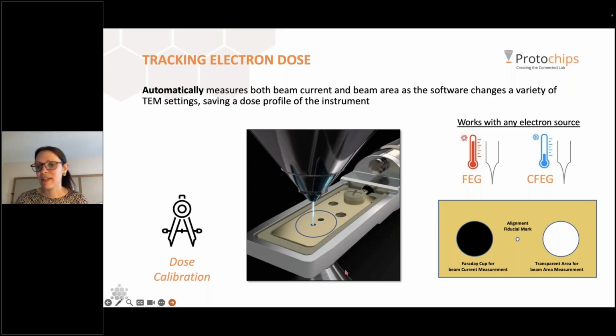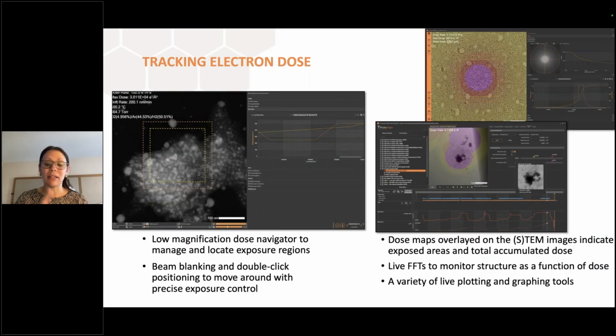Then you would remove this Faraday cup holder from the microscope and put the Triton holder in, or you could put one of your standard holders in, and you would have automated dose calculations and automated dose alignment with all of your images. Again, all of it recorded for you. Again, very important, especially in liquid cell for reproducibility. You get these colorized maps that help you visually see how much dose has been applied on a pixel by pixel basis. And because of the drift correction algorithms it's using, it remembers where the dose has been applied before.